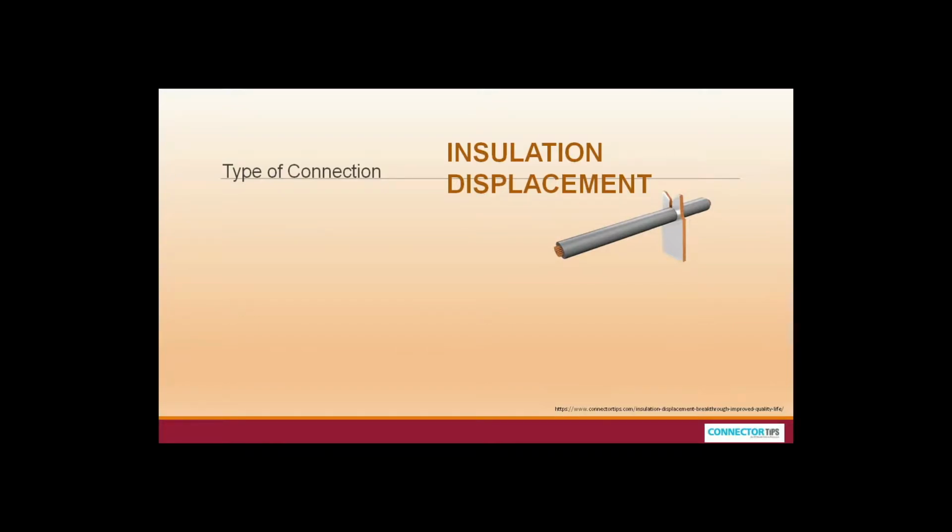The one thing I'm going to point out is that I got this from the internet, and you're going to be able to see the link when you download this presentation, this slideshow. I'm going to post it on our class portal. The one thing I want to point out is that right here, somebody included a stranded wire, a stranded conductor in the insulation. That is not correct.